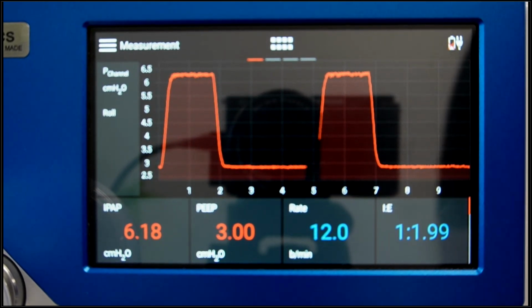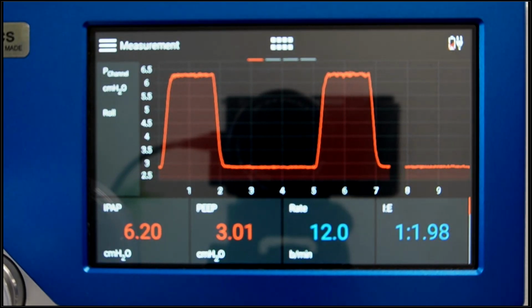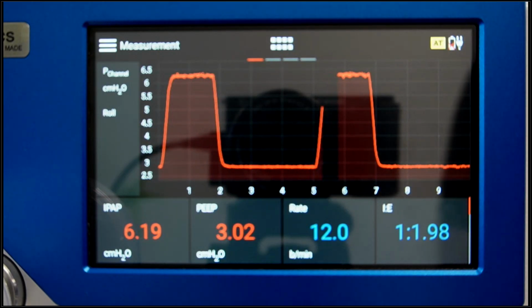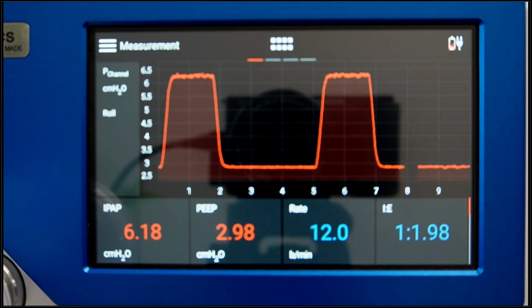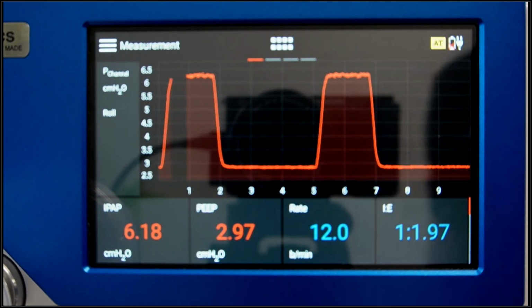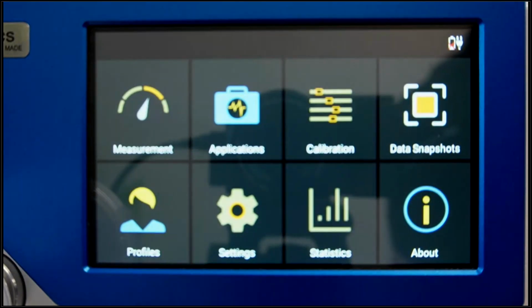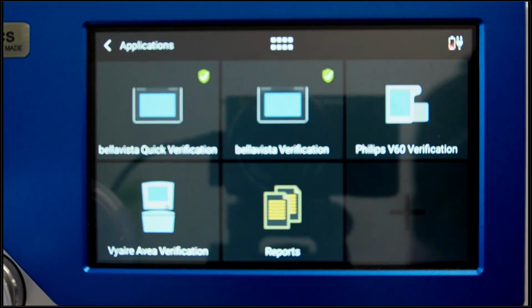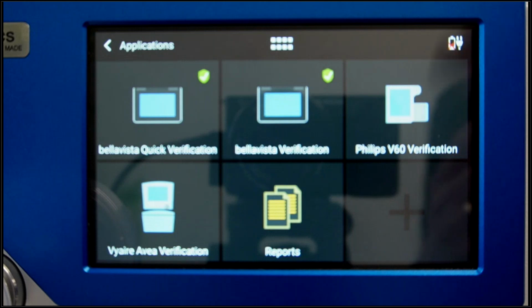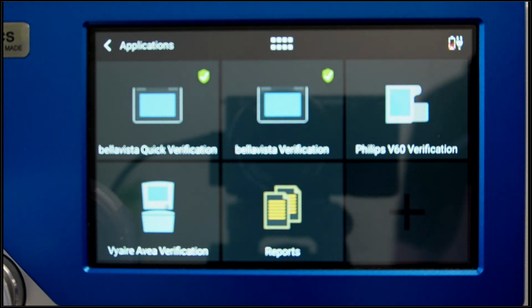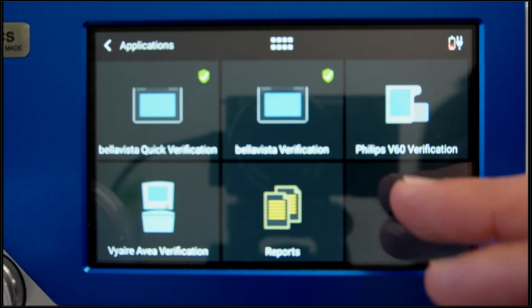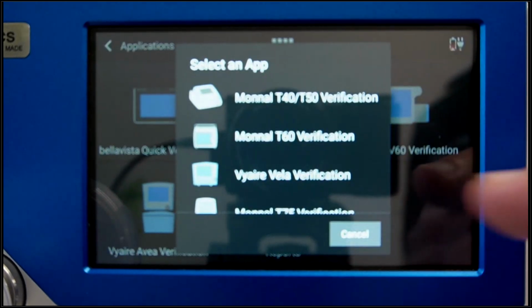And the last practical tip I wanted to share with you is actually a feature that is offered by advanced state-of-the-art gas flow analyzers, which actually addresses all the challenges we have discussed today. It's to use ready-to-use ventilator-specific testing applications or test sequences. So what we do on our latest devices, Citrex H5 and this Flow Analyzer Pro here, is we build, together with the ventilator manufacturer, their service procedure into a guided app on our device. So we have a library of them already, and that's going to grow over time.